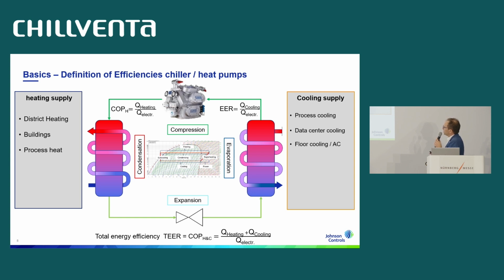Therefore the EER is the definition of the energy efficiency ratio, which is the useful cooling divided by the electrical effort. If you are talking about a heat pump, the useful heat is on the condenser side, and we are talking about a COP, a coefficient of performance, which is the useful heat divided by the electrical consumption. The heating supply can be district heating, buildings, or process heat. On the other side, there is process cooling, data center cooling, floor cooling, or AC. If you put both together, you have the total energy efficiency ratio, the TEER: the useful heating and useful cooling divided by the electrical effort. So keep that in mind. The TEER is a very important number. I will stress it a little bit more.